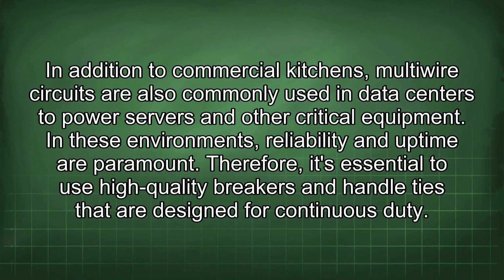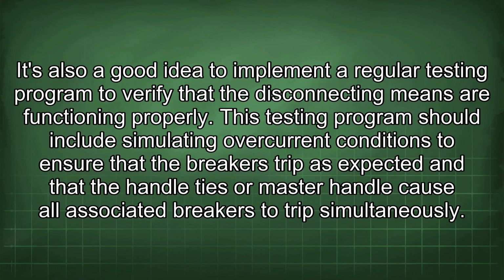In addition to commercial kitchens, multi-wire circuits are also commonly used in data centers to power servers and other critical equipment. In these environments, reliability and uptime are paramount. Therefore, it's essential to use high-quality breakers and handle ties that are designed for continuous duty. It's also a good idea to implement a regular testing program to verify that the disconnecting means are functioning properly. This testing program should include simulating overcurrent conditions to ensure that the breakers trip as expected and that the handle ties or master handle cause all associated breakers to trip simultaneously.